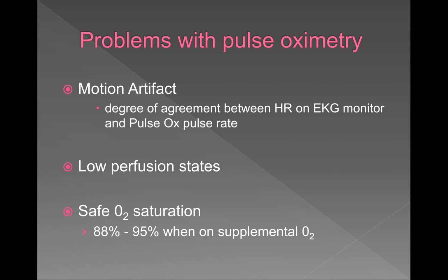And it's completely wrong. I thought they had special pulse ox sensors for neonates to go on the forehead. And adults. So if you have one that's designed for the forehead, then yes, you can use that. But you can't take one that goes around the finger or the foot and put it on the forehead. Right. You've got to make sure you have the right one.